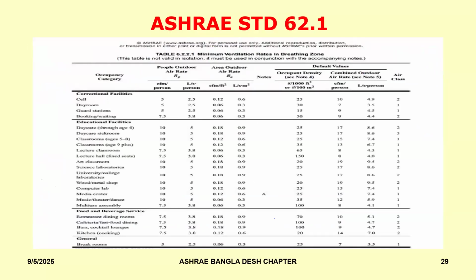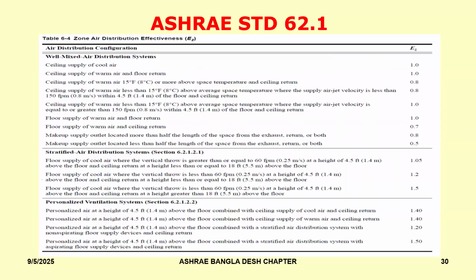So this is a table that provides you for various kinds of spaces that you are designing. See on the left hand side, for example, I've just taken a small extract, but it runs into a couple of pages where you'll find all kinds of application. And it gives you the amount of CFM per person that you should have, and the CFM per square foot for the area. These are default prescriptive numbers. You could use these and simply say that as per the standard, this is the minimum ventilation that I require to provide. Now, apart from this, 62.1 also says that merely putting that number by itself is not correct.